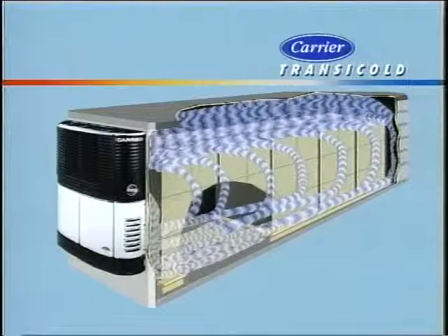Pressing the select key once brings up the pre-trip selection. The message center will show press equal to start pre-trip. If the equal key is pressed, the unit will go into the pre-trip test mode. The message center will show test number 1 display. During this time, the entire keypad will light up. You'll need to verify this portion of the test.